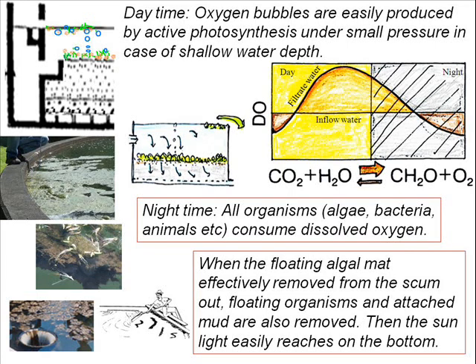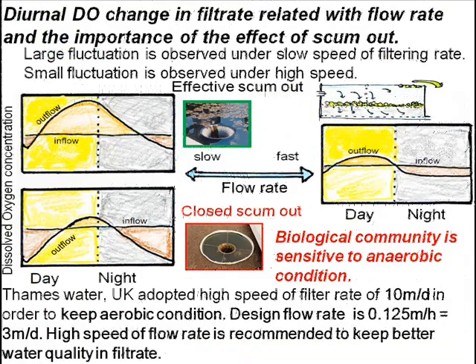In the daytime, oxygen bubbles are easily produced by active photosynthesis under low pressure in shallow water depth. In the nighttime, all organisms consume dissolved oxygen. When the floating algal mat is effectively removed from the scum outlet, the floating organisms and attached mud are also removed, then sunlight easily reaches the bottom again and algae at the bottom grows again. A diurnal change in filter rates related to flow rates shows large fluctuation under low filter rate and small fluctuation under high speed.